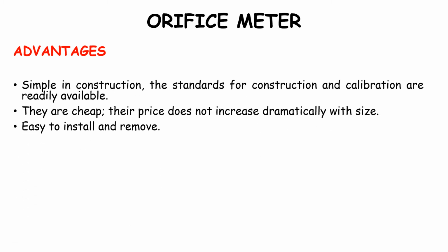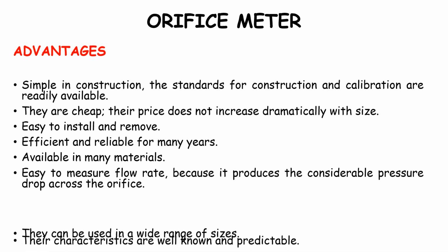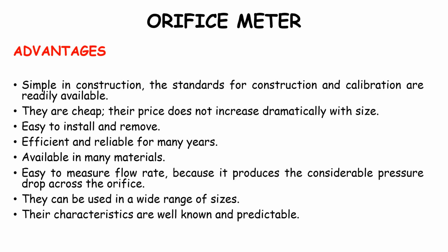So moving on to the advantages. It is very simple in construction. Standards for construction and calibration are readily available. They are cheap. Their price does not increase dramatically with size. Easy to install and remove. Efficient and reliable for many years. Available in many materials. Easy to measure flow rate because it produces a considerable pressure drop across the orifice. They can be used in a wide range of sizes. The characteristics are well known and predictable.